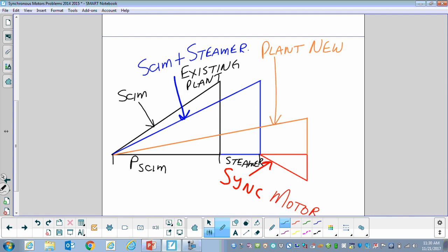Now, all we're doing when we go to the blue triangle is we're adding more P, more power. We're not actually adding anything reactive, so that's why the height of that triangle hasn't changed. Then when we add the synchronous motor on, clearly a synchronous motor has two circuit properties - we have resistance and we have some sort of reactive component. So when you take the red guy and add it horizontally and take the vertical component, which is opposite to our inductive component, you can see that we are left with this right here.